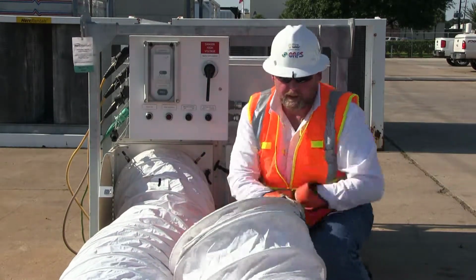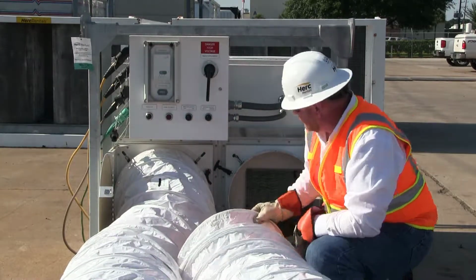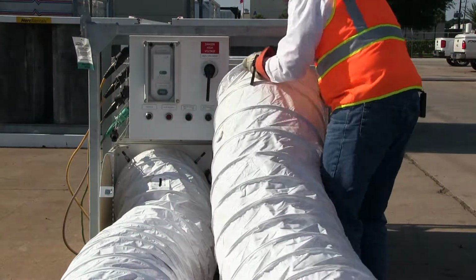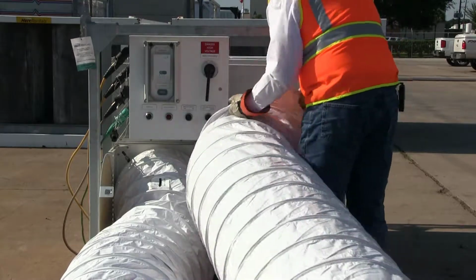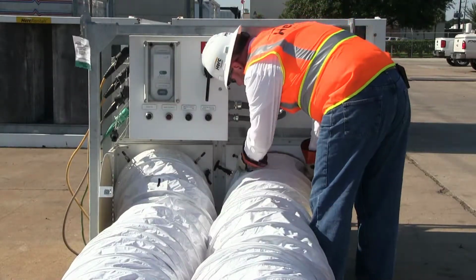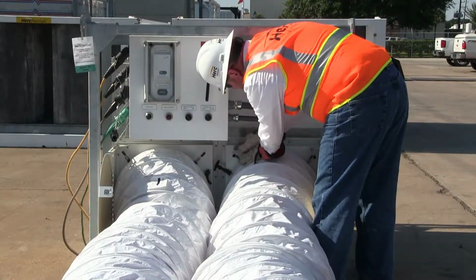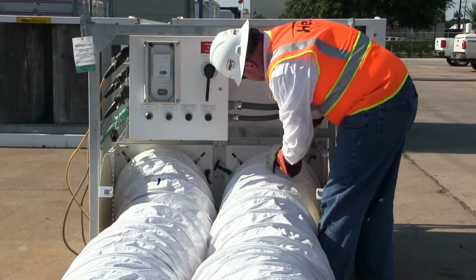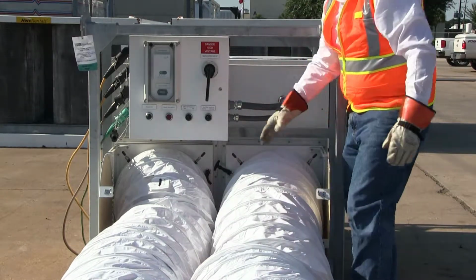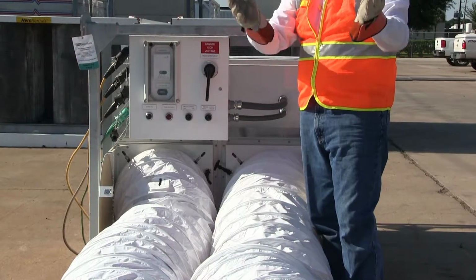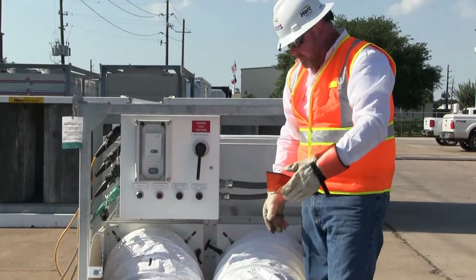Now this duct is coming too, so the arrow is going the opposite direction. So this duct will just come in here to the bottom, and I usually hook up the bottom rings first, follow it over to the top, and then we'll bring all four of the friction clamps down. Then these two ducts will go into the conditioned space and provide cooling on one side while returning hot, moist air on the other side.